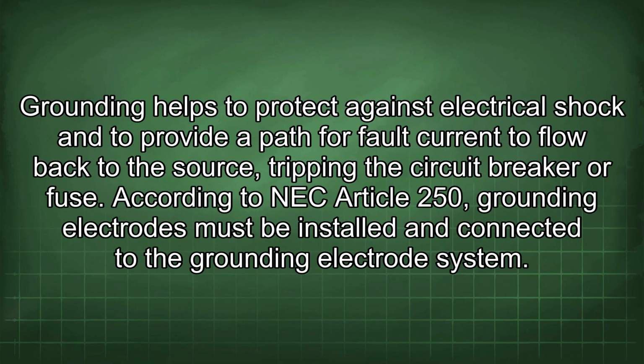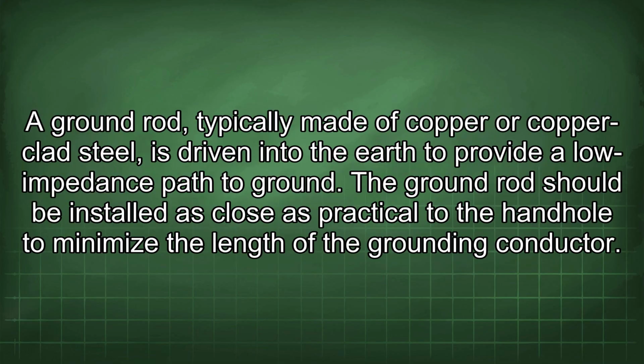Grounding helps to protect against electrical shock and to provide a path for fault current to flow back to the source, tripping the circuit breaker or fuse. According to NEC Article 250, grounding electrodes must be installed and connected to the grounding electrode system. A ground rod, typically made of copper or copper-clad steel, is driven into the earth to provide a low-impedance path to ground.